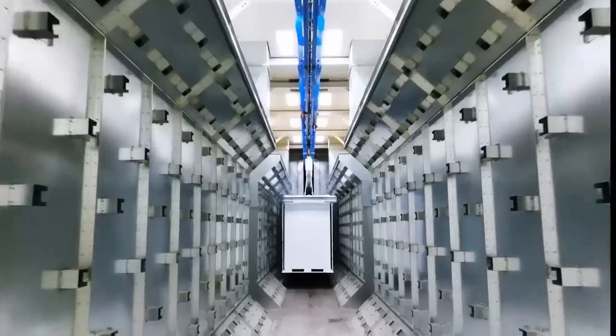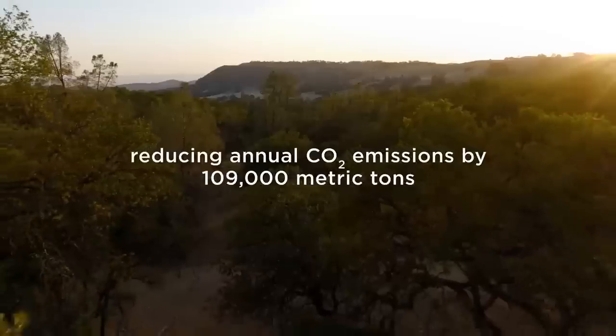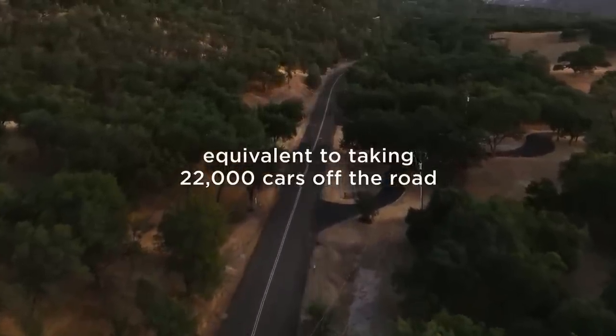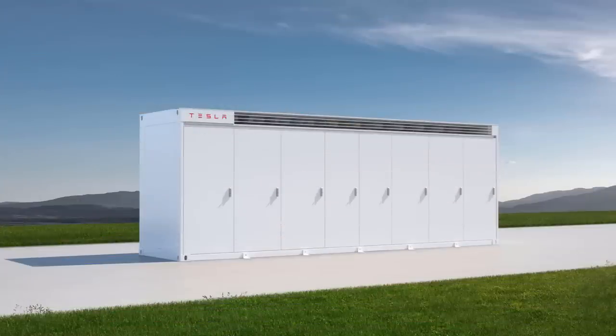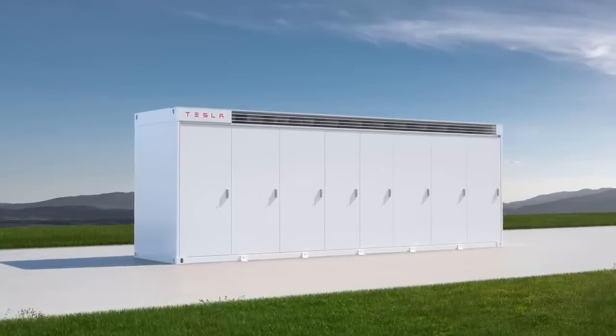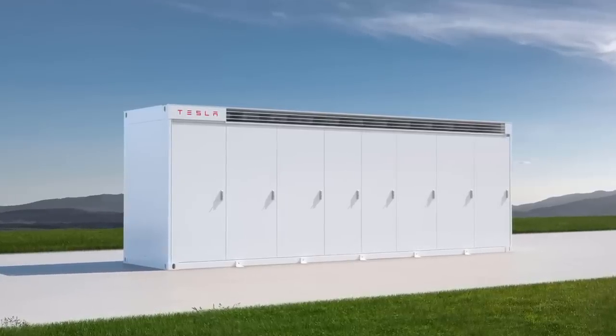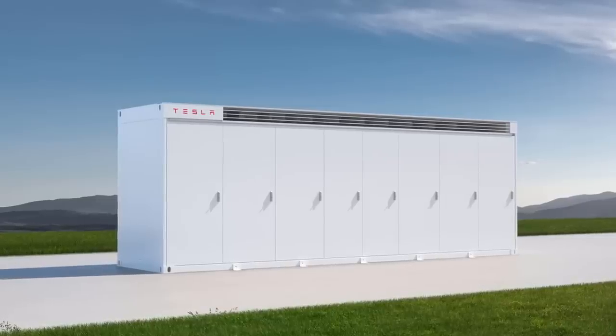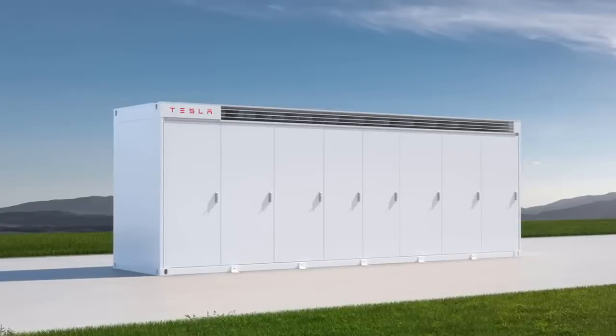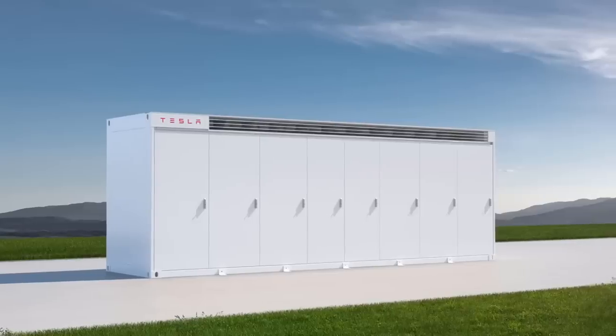The battery facility in California became operational in 2022 and is said to have cost over $100 million, reducing annual CO2 emissions by 109,000 metric tons — equivalent to taking 22,000 cars off the road. This project doesn't make use of Tesla's latest Megapack technology, since Erevon ordered the batteries in 2021. The original Megapack was a 3 MWh system, while today's Megapack is a larger 3.9 MWh, which is why the reported 85 Megapacks roughly add up to 240 MWh of capacity. Erevon was paying about $1.17 million on average per Megapack, while today's prices are much higher but for a larger pack.